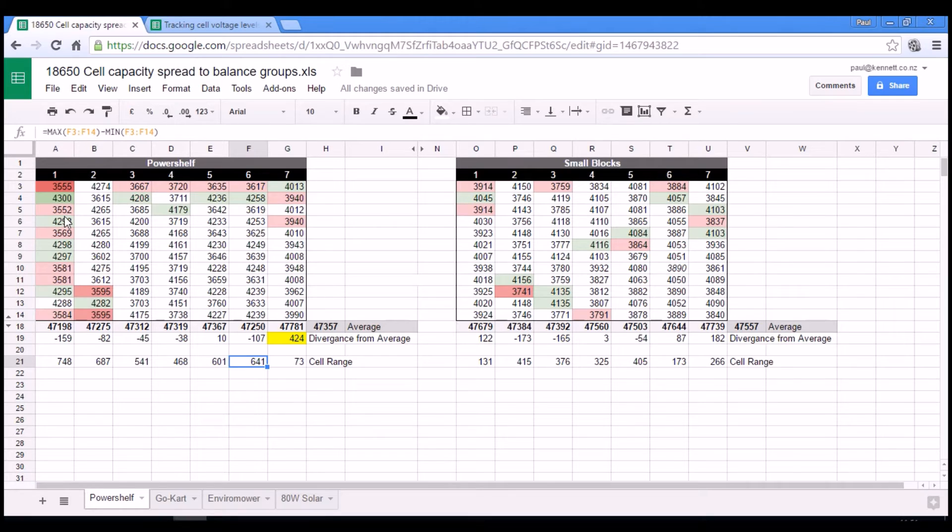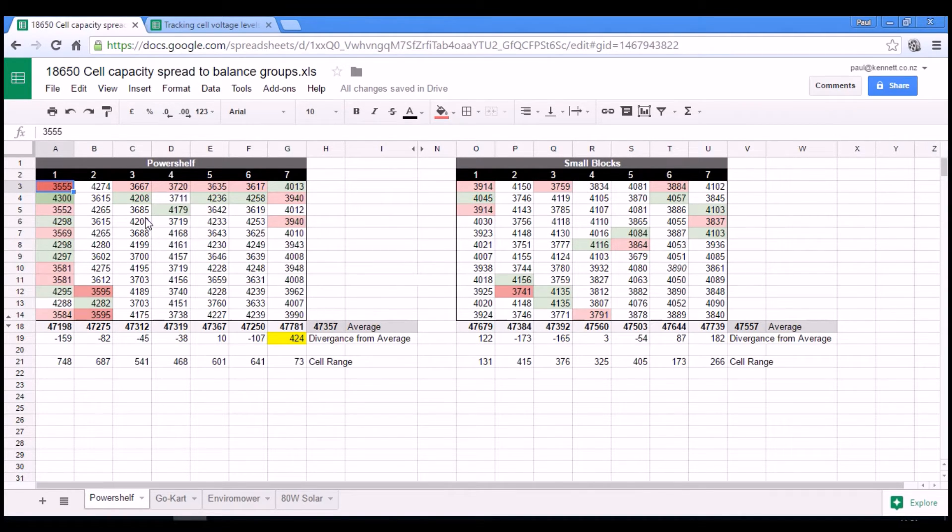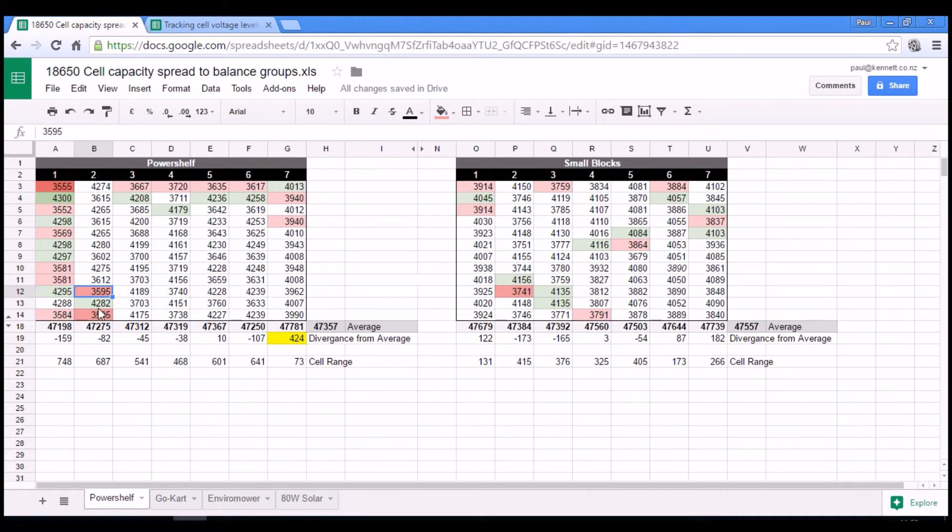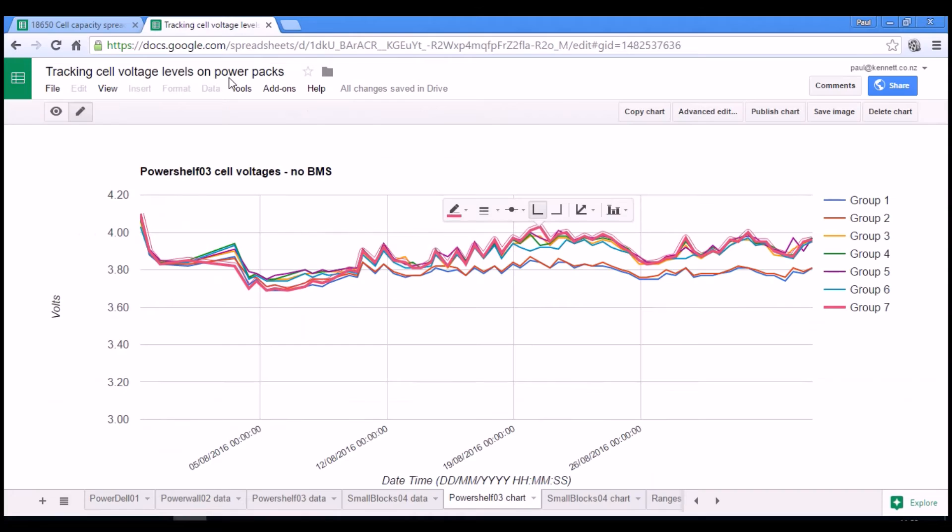What is really distinctive about these two groups here is they have the single lowest capacity pair of all of the two packs and certainly within the power shelf. And the next lowest are these two here in group two. So I think those are the ones that are causing these to sag.